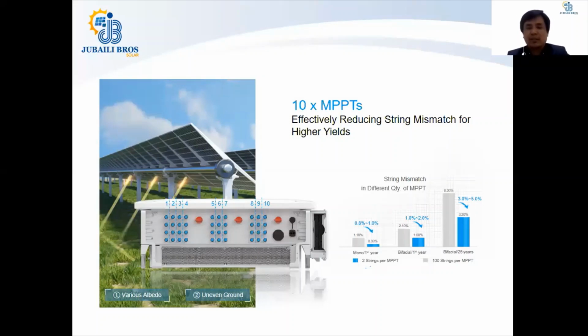I would like to draw your attention to the inverter bottom side. As you can see, the inverter has 3 red switches. These are the DC switches, and you can turn these DC switches on and off at a particular time of the day when the generation current is just below 0.5 ampere. I am telling you this because most installation people disconnect it at a time of day when the current is very high, and arcing can happen, which can damage the inverter board. Inverter AC cables get connected on the right side. The blue points which are shown are actually the DC connection points, and the small black point which you can see is for the cable.